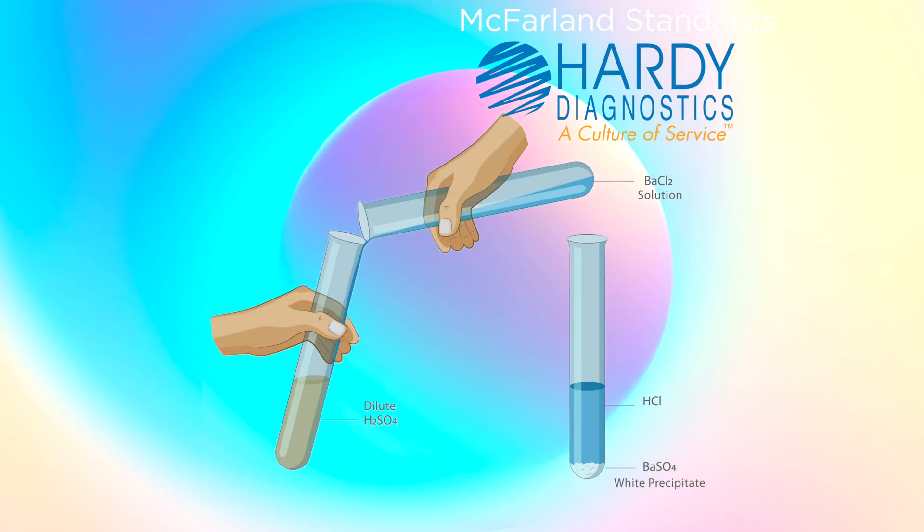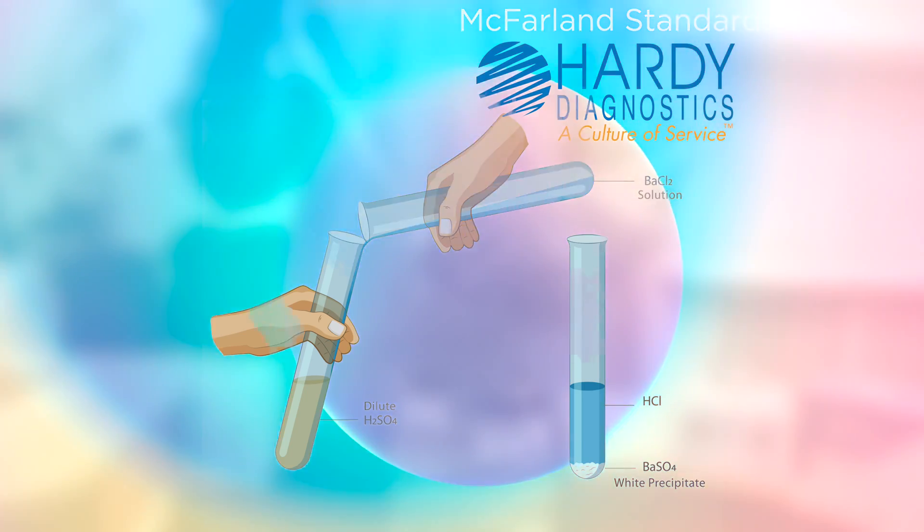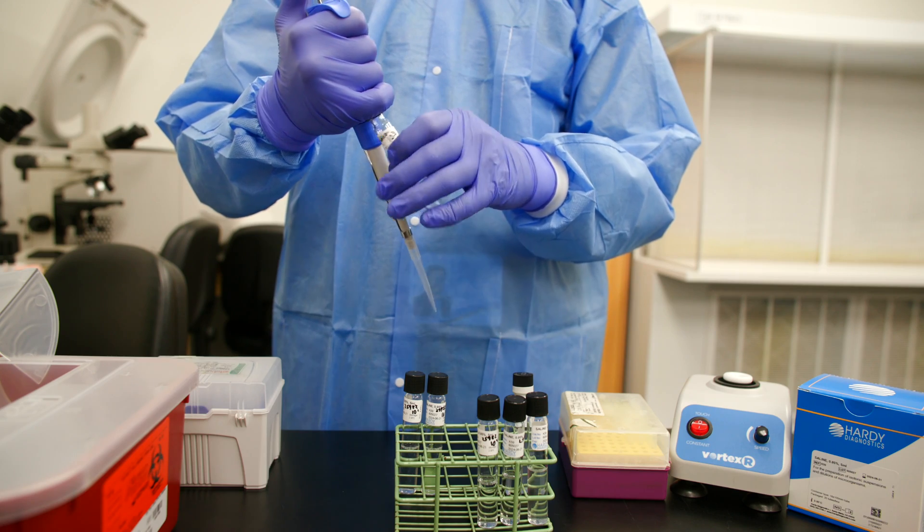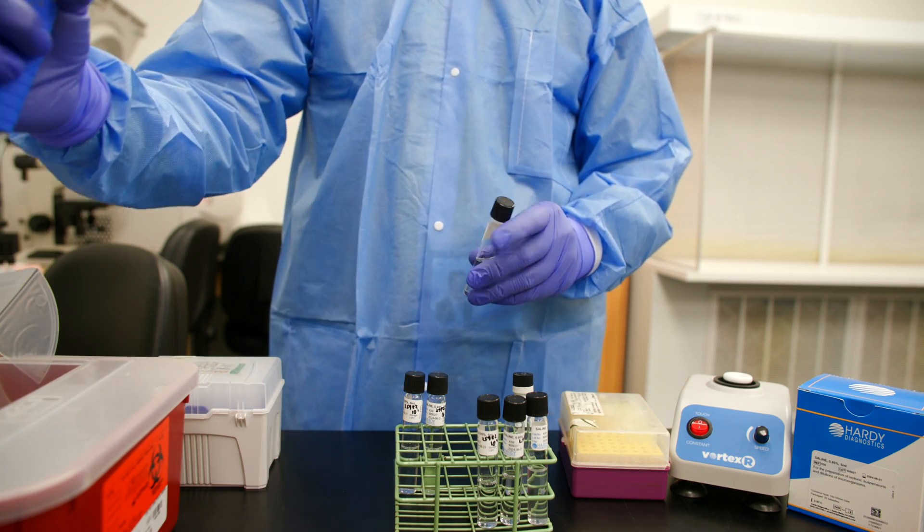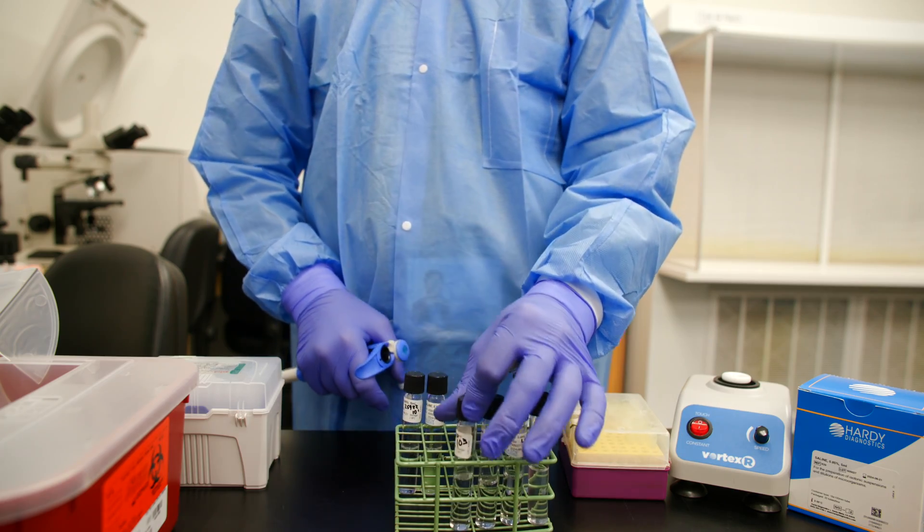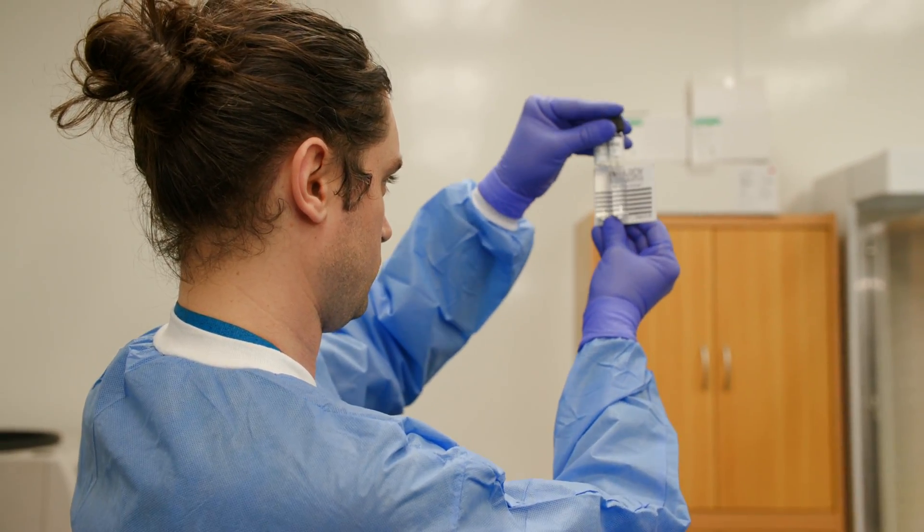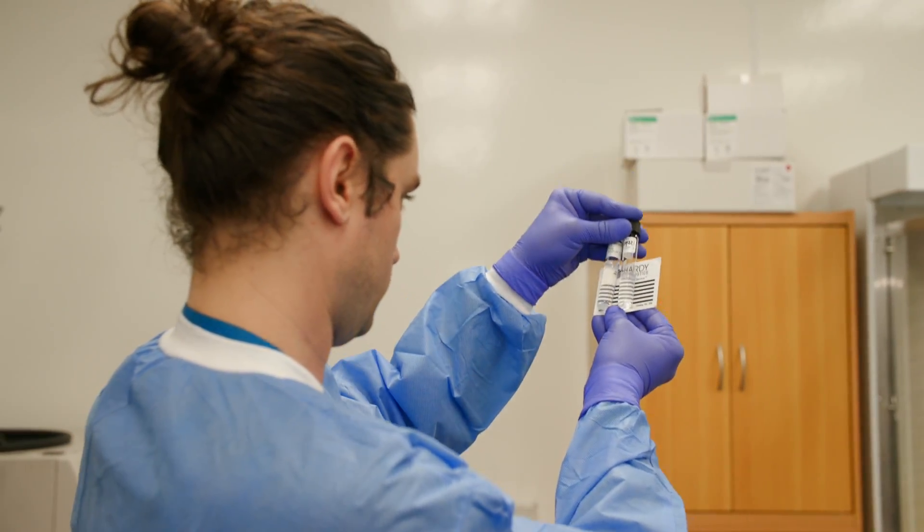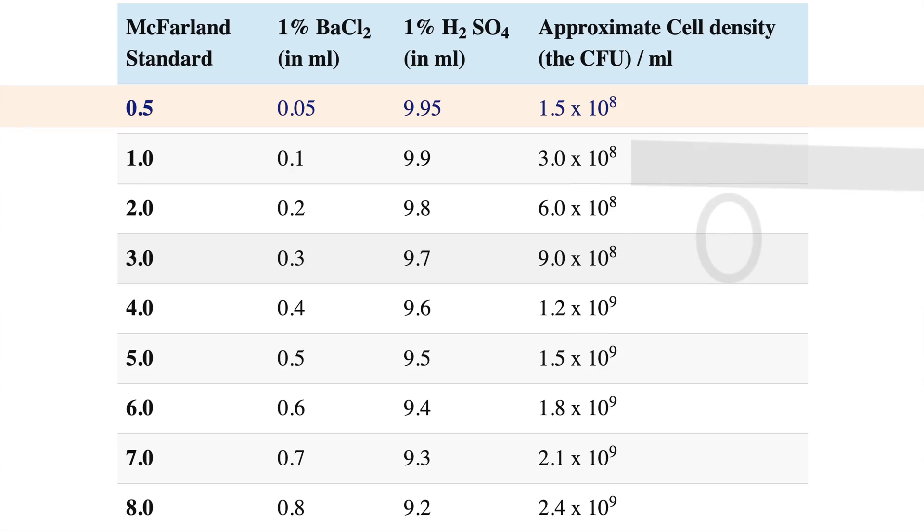McFarland standards were originally prepared by adding barium chloride to sulfuric acid resulting in a turbid barium sulfate precipitation. Today the use of latex particle suspensions is widely accepted since latex beads are far more stable. McFarland standards are commercially available from concentrations ranging from a 0.5 standard to an 8.0 standard.